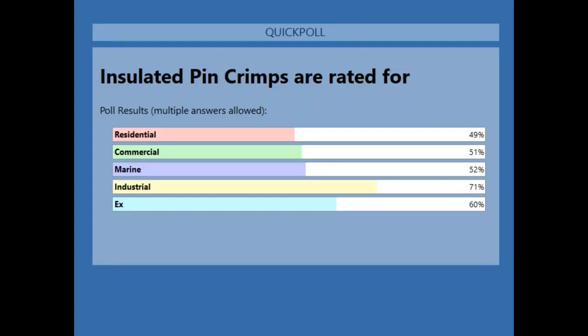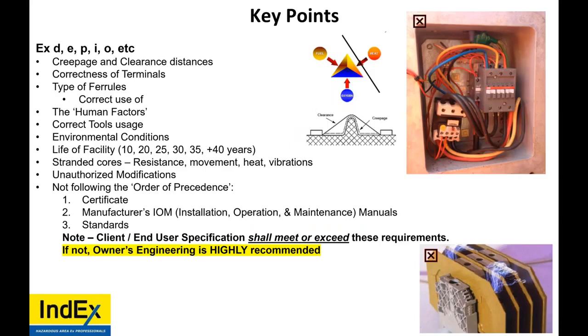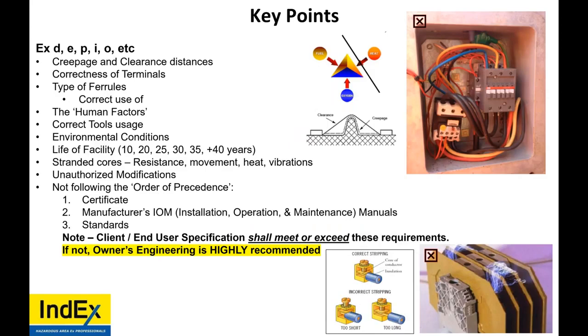Now, perhaps the understanding of insulated pin crimps, you'll find out in the next slide. Insulated pin crimps are primarily a commercial and marine use termination. We'll go over why. So, also another importance, correctness of stripping. Too short, you're terminating on insulation. So when we're mentioning insulated pin crimps, they are rated for marine and commercial, therefore also residential use. Now, also importance for stripping is if it's too long, your creepage and clearance distances are now too short. If you terminate on insulation, obviously you're damaging the insulation of the core, and you're going to have high resistance.